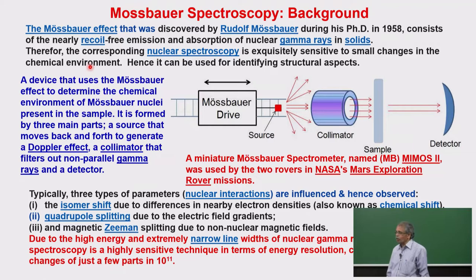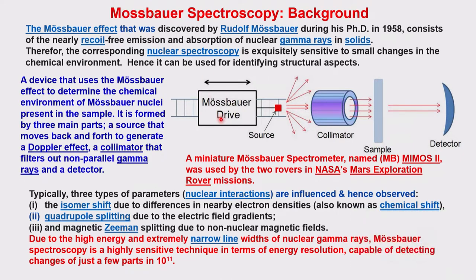In terms of measurement, you have what is called the Mössbauer source. There are three major components of the instrumentation. You require a gamma ray source (the Mössbauer source), your sample which is the absorber, and a detector to capture what comes out. Non-parallel radiation can be eliminated using a collimator. The sample must be placed in the beam path, and whatever passes through is measured by the detector.